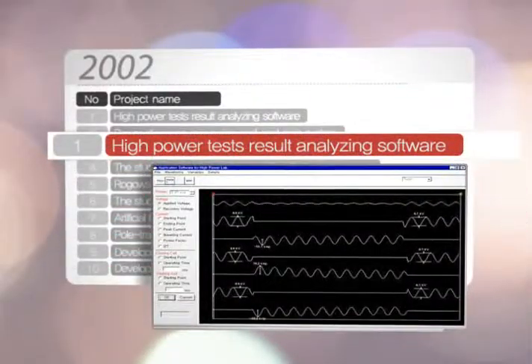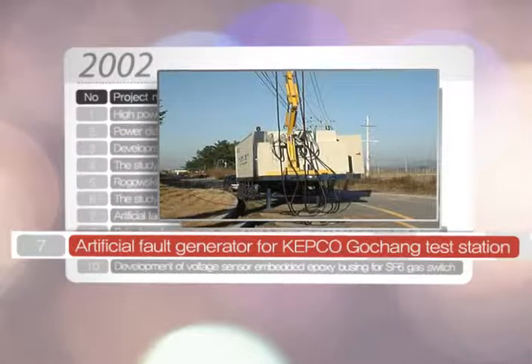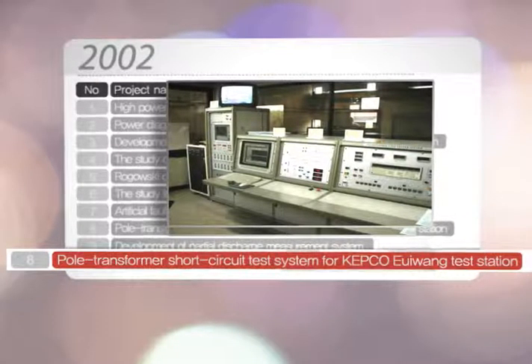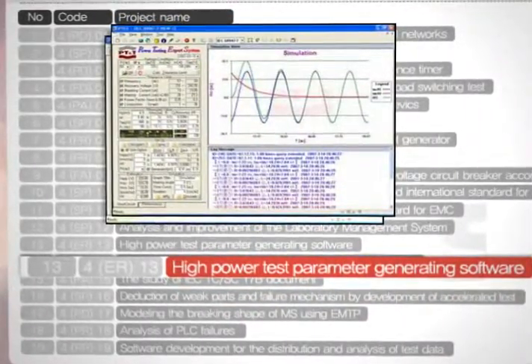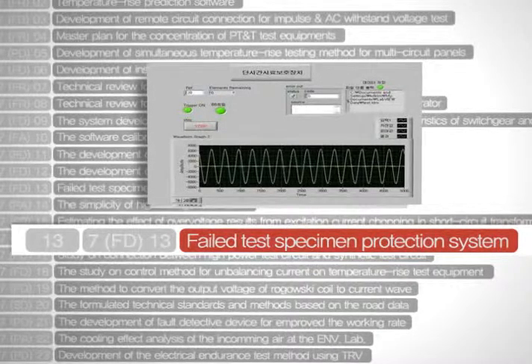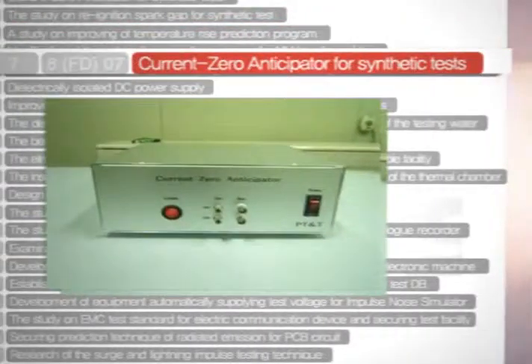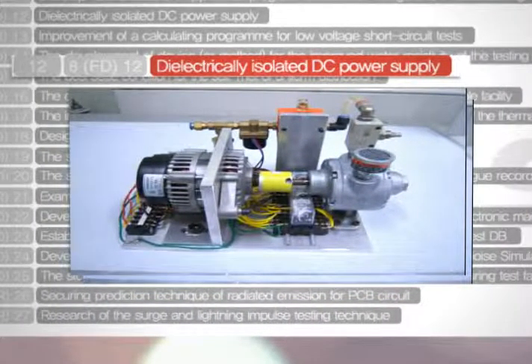PT&T also performs research and development work to shorten test time, save investment, develop necessary techniques in advance, and provide solutions for failed tests. For example, high-power test result analyzing software and an artificial fault generator have been developed for KEPCO Gochang test station. A pole transformer short-circuit test system was developed for KEPCO Uiwang test station. In addition, a lightning impulse test software program, high-power test parameter generating software, temperature rise prediction software, and an apparatus to save failed test pieces for failure analysis have been developed. Furthermore, a four-parameter TRV generating method from a two-parameter TRV circuit, a current zero anticipator, and a dielectrically isolated DC power supply have also been developed.